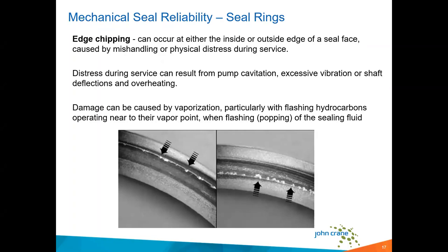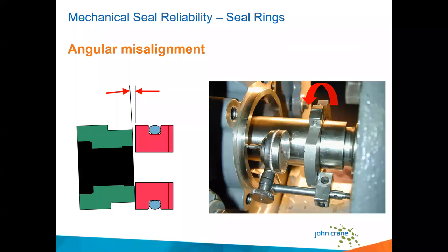And so this is what I was talking about earlier, that a lot of times these checks may get missed, or they may get, not that they get brushed off, but I've heard many times, we checked it last time, it was good, or no, that's not an issue. Even if it is good, we want to see the numbers, and we want to know what the actual readings are. So these are just some of the checks that we're talking about, and these are the bigger ones that are going to impact the life of your seal.